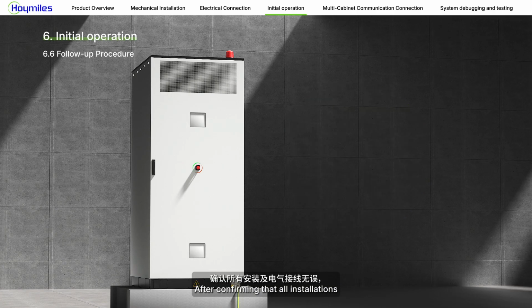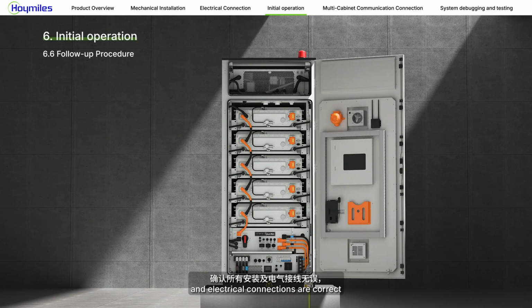After confirming that all installations and electrical connections are correct and that the trial operation is successful, perform the following steps. Use the fireproof sealing putty supplied with the equipment to seal the PCS cable routing openings. Use the fireproof sealing putty supplied with the equipment to seal the power cable and communication cable routing openings at the bottom of the cabinet. Install the bottom protective plates.